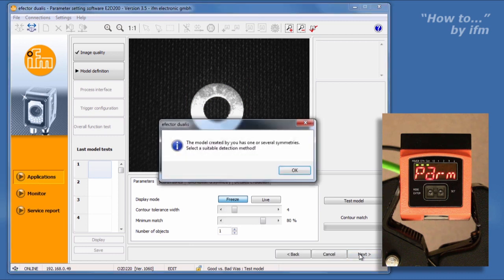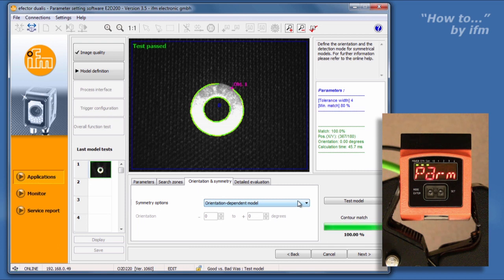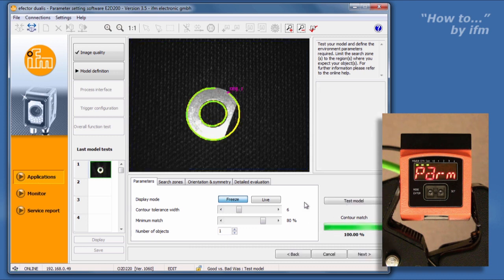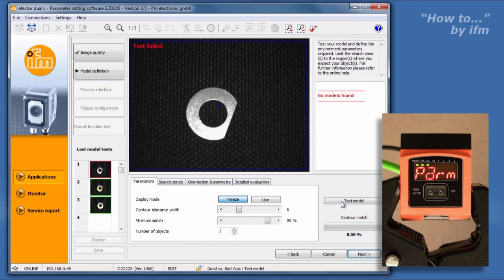Due to the fact that the model's contours are circles, we get a message to select a suitable detection method. Clicking OK will automatically open the Orientation and Symmetry panel. For this application, the default setting will be adequate. In the Parameters panel, you can adjust the tolerance width of the contours, indicated in yellow in the sensor's image area. Adjust the tolerance to allow for any variance that would still allow a part to be considered passable. Notice the default setting for minimum match is 80%. By placing a typical bad part in the sensing area and clicking Test Model, we see that a defective washer still matches more than 80% of the good washer's contour. To allow for this, I'll set the minimum match to 90%. When we click Test Model again, we see that the test failed. Replacing the good part and testing it again verifies that a bad part will fail the test while the good part passes.